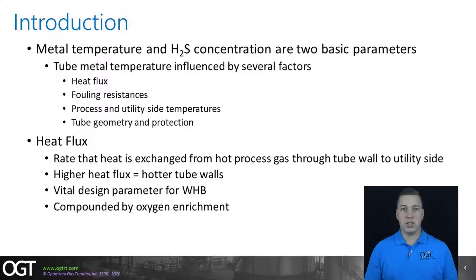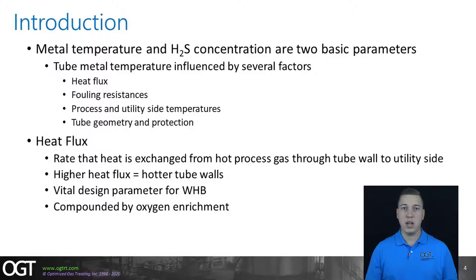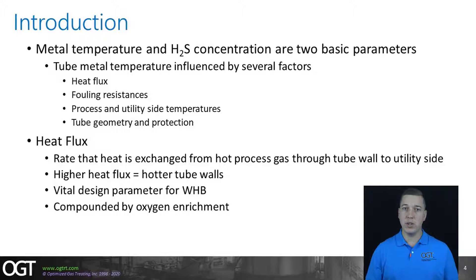We'll focus on heat flux for this discussion. Heat flux is defined as the rate at which heat is exchanged from the hot process gases through the tube wall and into the utility water, which ultimately carries that heat away in the form of steam. The higher the heat flux, the more heat is being passed through the walls, and so the hotter those walls become. This can pose a real threat to the integrity of the boiler tubes due to increased risk of corrosion, and is one of the many vital design parameters that engineers look for.